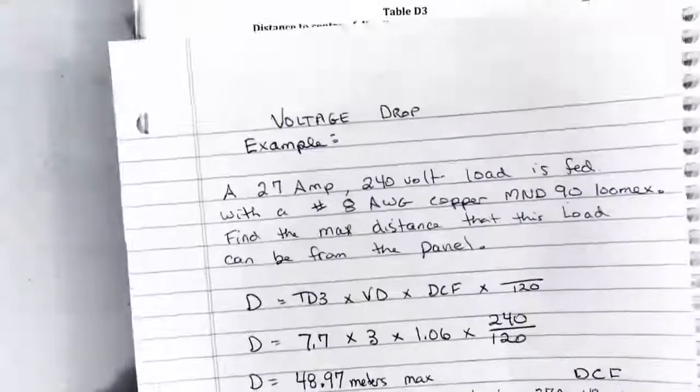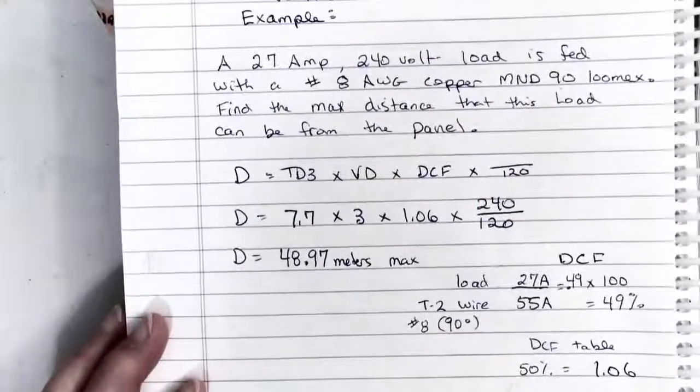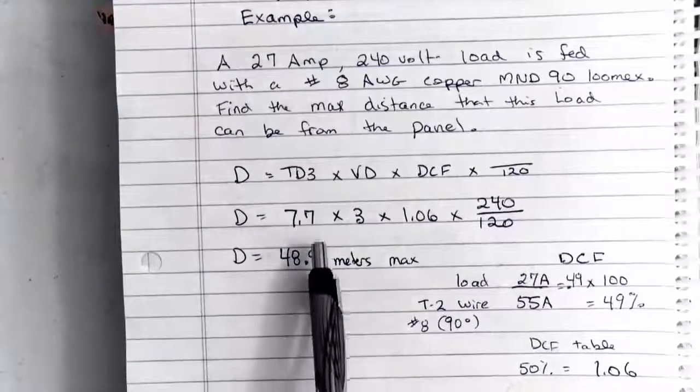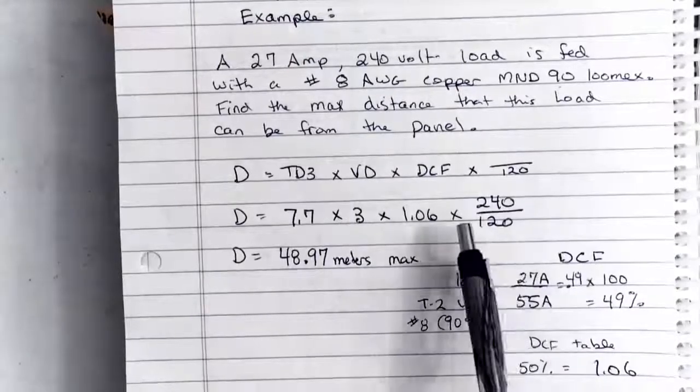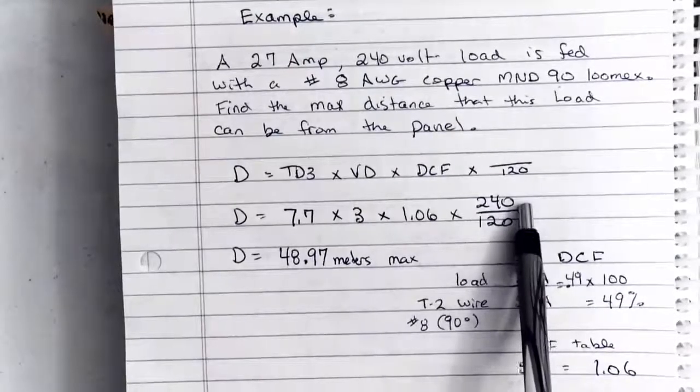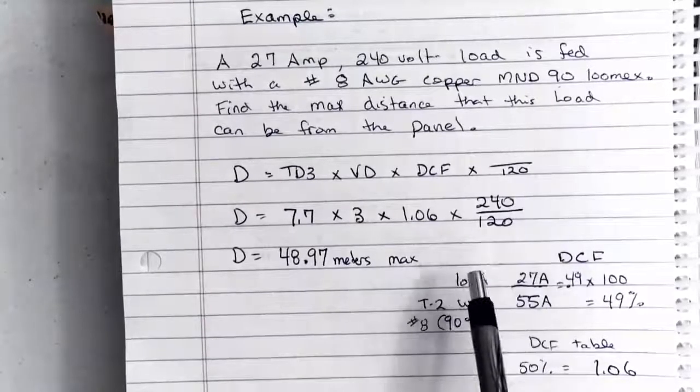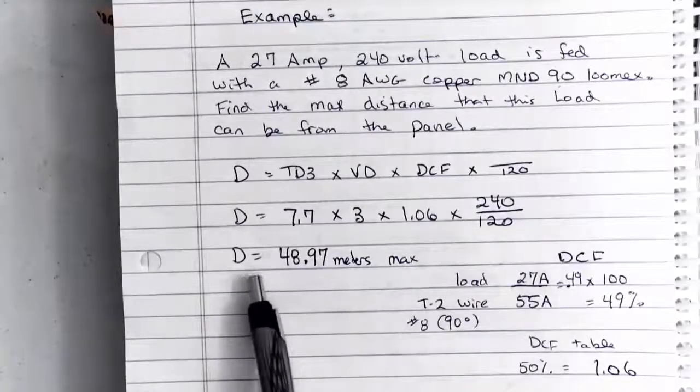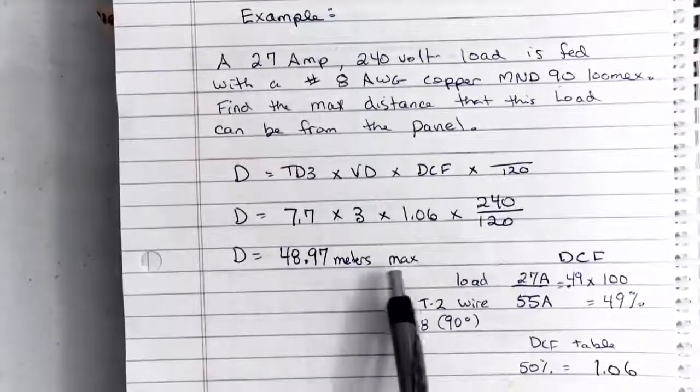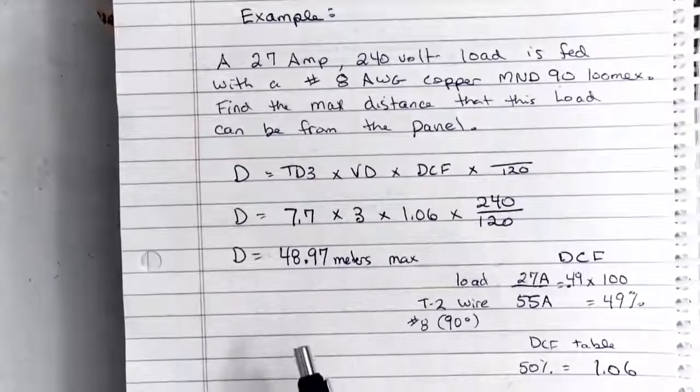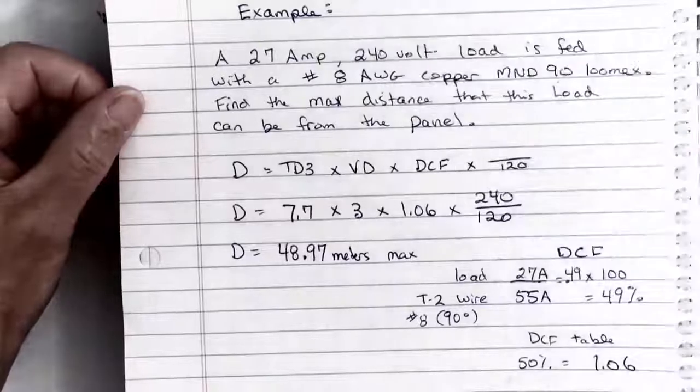So now I had the 1.06 which I found with my distance correction factor by going to the table. And the last piece was I was given 240 volts as my supply. I divide that by 120 to adjust this formula. And when I multiply all this out, I end up with 48.97 meters is the maximum distance that I could use a number 8 copper conductor to feed this 27 amp load.